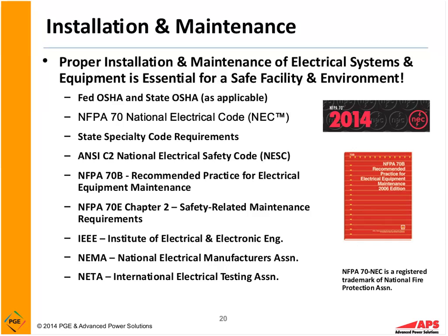NFPA 70B, Recommended Practice for Equipment Maintenance, shows us how to maintain our equipment. We have NFPA 70E, Standard for Electrical Safety in the Workplace, which just touches on safety. And we have other standards such as IEEE, NEMA, and NETA, which all get into safe maintenance requirements and so forth. These are very important for us to follow.